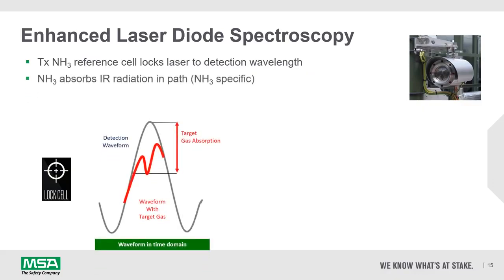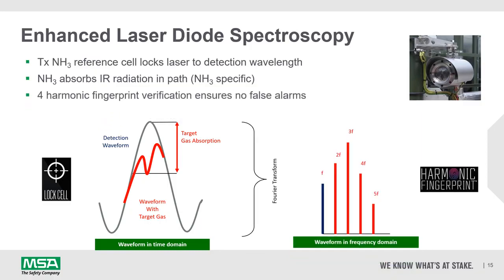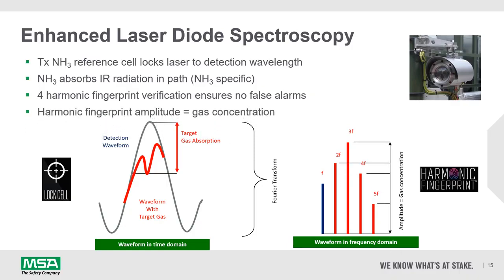The infrared light from the transmitter is sent to the receiver, and due to the absorption of that infrared light by the ammonia molecules, the signal becomes distorted. At the receiver, a technique called Fourier transform, typically used by laser-based process analyzers, converts that distorted signal into its component parts, called harmonics. The pattern of harmonics is known as a harmonic fingerprint, and the amplitude of that harmonic fingerprint is proportional to gas concentration. And again, this is ammonia specific, so there are no cross interference or cross sensitivities.